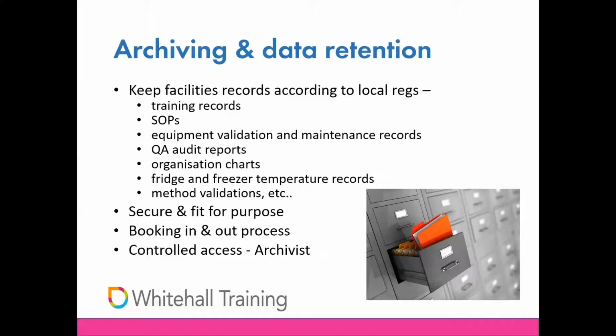One thing to particularly bear in mind with lab work, there are some types of paper records that need special consideration, like things that are produced on heat-sensitive paper by thermal printers. Now, I don't know if you've ever dealt with those, but it's a known fact that these will fade over only a few years. So you must have steps in place if you're going to be dealing with these type of records that they can be safeguarded in a formally controlled way, such as making certified copies at an early point while they're all still legible.